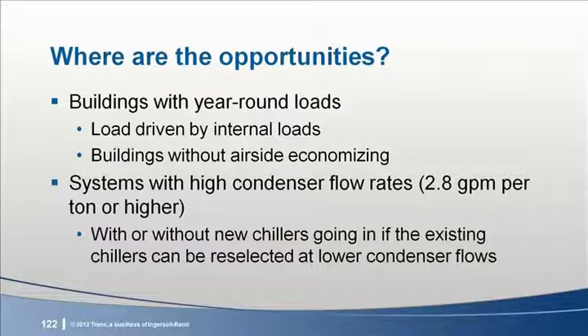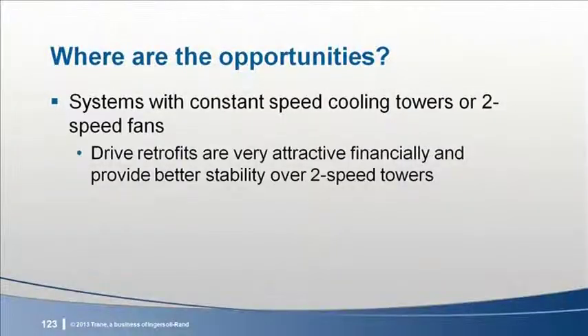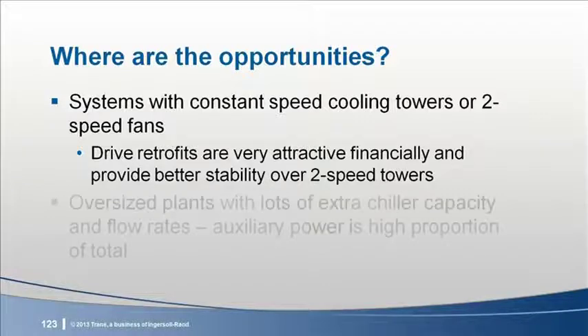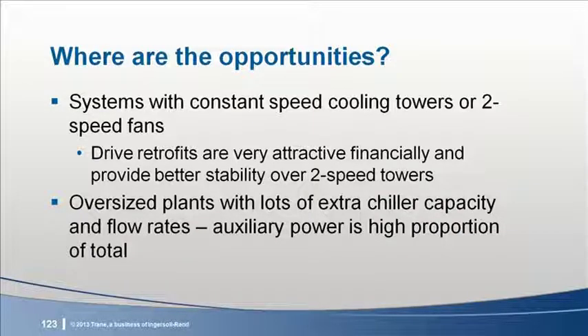As we saw on mixed slides, the time is ripe when new chillers are going in. But even if you aren't installing a new chiller, if you control it properly, you can turn that high flow system into a low flow system a lot of the time. Another candidate, systems with constant speed cooling towers, or those with 2-speed fans. Drive retrofits on cooling tower fan motors are very economical for the benefit that they bring. They're also attractive as a retrofit on a 2-speed fan motor because the control won't hunt and the system will have better stability.